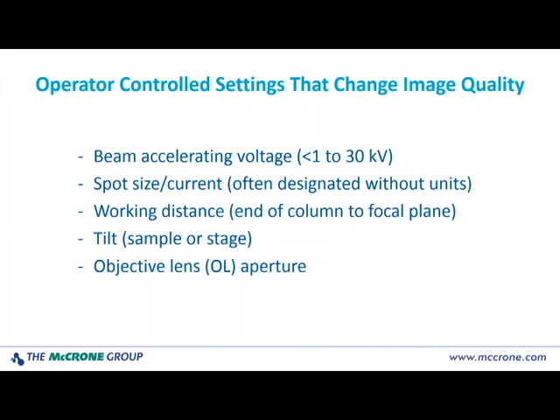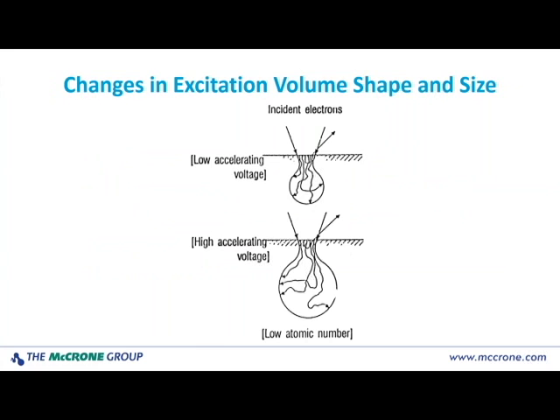So if you can tilt it just a few degrees sometimes, you can get an amazing effect on image quality. We also want to take a look at our objective lens, if this is available on your instrument for adjusting. As you change the size, you can affect the image quality. First, we'll take a look at what happens to our excitation volume if we're looking at low atomic number material.